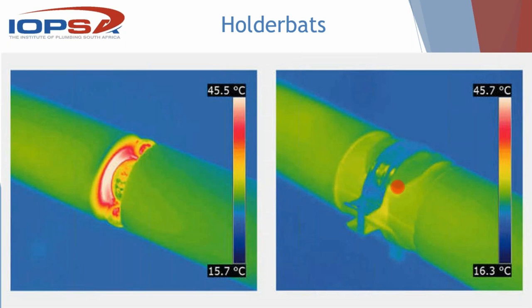They say that you must lag all exposed water pipes. Hot water pipes must be lagged. So to lag a 22 millimeter hot water pipe in a single wall is impossible, because the lagging material is 75 mil. A wall is only 110 mil. I mean, you might as well cut the whole wall in half. So obviously that's unrealistic. So good practice is just to wrap it up in something to insulate it from, not insulate it, but isolate it from the cement.